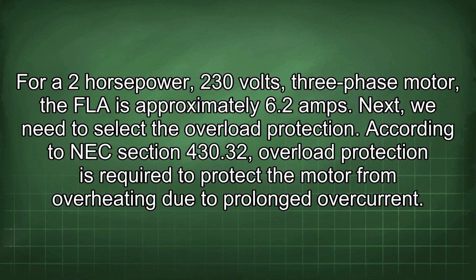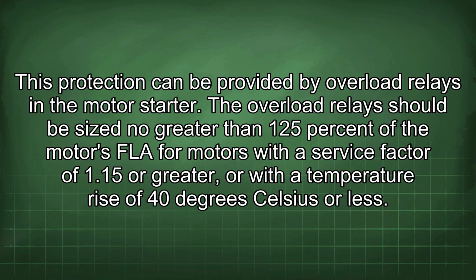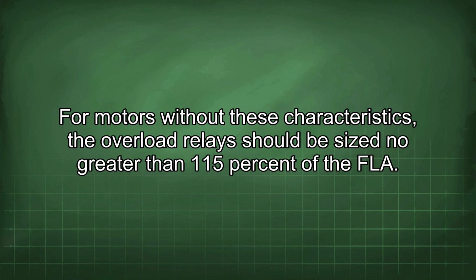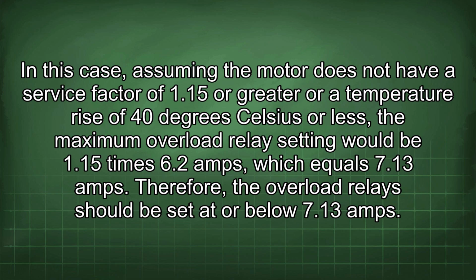Next, we need to select the overload protection. According to NEC Section 430.32, overload protection is required to protect the motor from overheating due to prolonged overcurrent. This protection can be provided by overload relays in the motor starter. The overload relays should be sized no greater than 125% of the motor's FLA for motors with a service factor of 1.15 or greater, or with a temperature rise of 40 degrees Celsius or less. For motors without these characteristics, the overload relay should be sized no greater than 115% of the FLA. In this case, assuming the motor does not have a service factor of 1.15 or greater or a temperature rise of 40 degrees Celsius or less, the maximum overload relay setting would be 1.15 times 6.2 amps, which equals 7.13 amps. Therefore, the overload relays should be set at or below 7.13 amps.